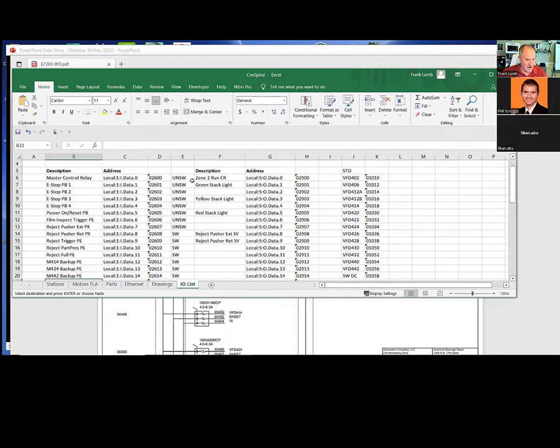outputs starting right here. I've got a run control relay back to zone 2. This is the thing that tells zone 2 to stop. So if it doesn't have this input, that means that the zone 3 is not on. So you notice I didn't put this zone 2 stop. I made it run, right? So if that disappears, somebody cuts the line, that stops zone 2. That's the way we want to do it.